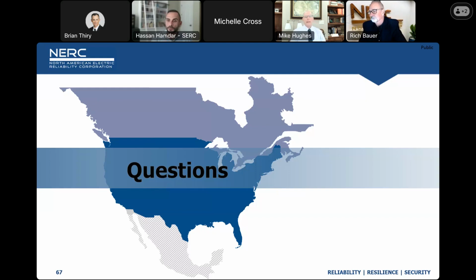Rich, I think it did. The next two are paired up as well. I think you've already answered the first one, which was, do we need better load modeling for large loads? And the one that pairs with that is, from your conversations with the load centers, did their electrical engineers give you any idea as to how sensitive those loads were? Like, we know it was three strikes you're out, we know it was a voltage dip, but did they give you a sense of the percentage of voltage dip that would trigger that response?